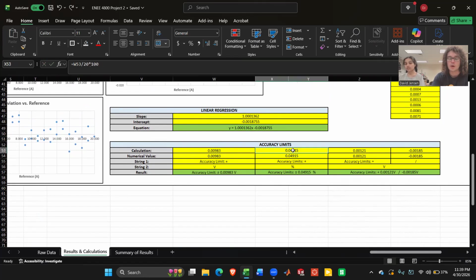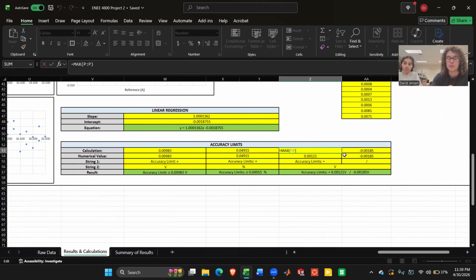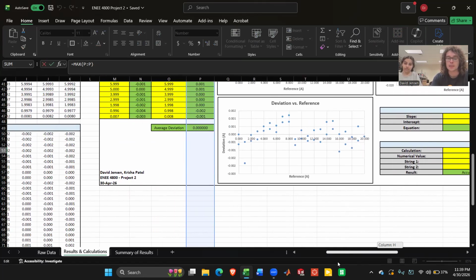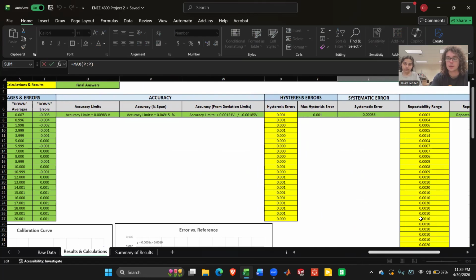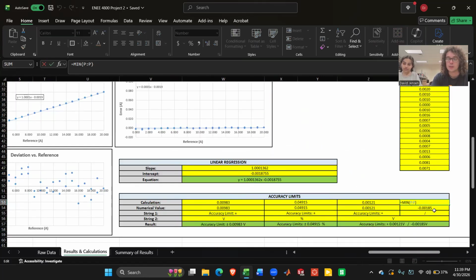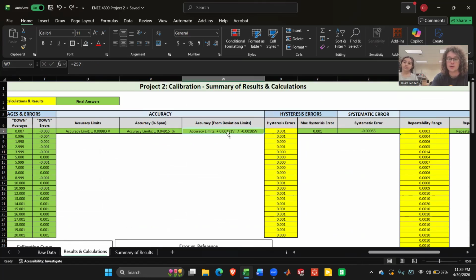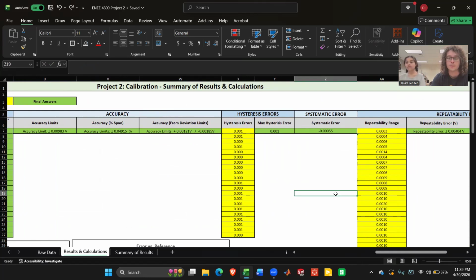The next column here is our percent span, and that just uses our absolute value, divides it by 20 to normalize it, and then multiplies it by 100 to get a percent. And then for our deviation limits method, we just take the maximum of our deviation column and then the minimum of our deviation column, and we apply that. So our upper bound is this one and our lower bound is this one, as you can see here. And again, that gives a better approximation of the accuracy since it's not symmetrical around the measured point.